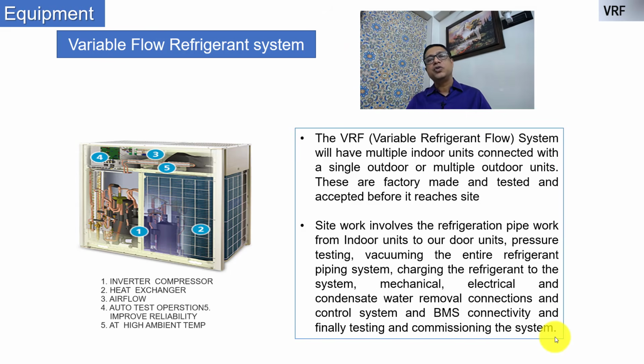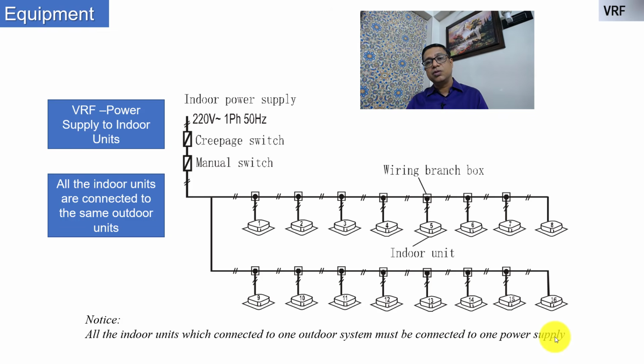It's a system which has multiple indoor units. Different types of units can be connected to one outdoor system. Generally we have one to one, and that's where this system got more and more momentum. This involves a lot of refrigerant piping work, mostly of copper material, and that's one of the important aspects when it comes to VRF. With lots of piping, the refrigerant moves through that piping, the leakages can become very severe, and you also need proper resources to do this refrigerant piping properly. It is not the soft piping, it is mostly the hard piping.